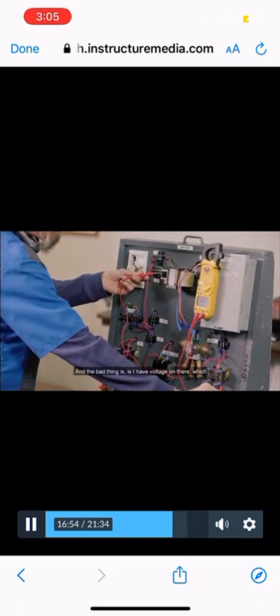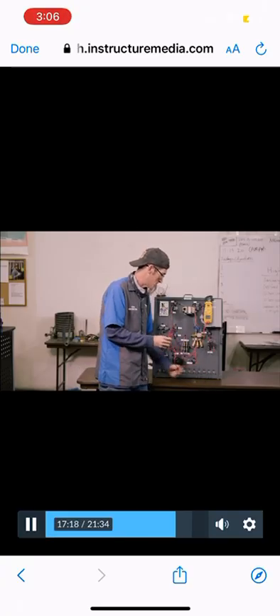So what I'm going to do is check this blue wire first, and I'm going to go from point A over here to point B over here, and I'm looking for 0 because that would be a good wire. And I have 0, which means that wire is okay. So I have to check the other side. So I'm going to go from this terminal here up to the common on my transformer. I'm looking for 0, and the bad thing is I have voltage on there, which tells me that the wire going from here back up to here is broken, and that's what's preventing this from getting any power. So the students would log that in the field. We would fix that wire. You'd be able to see it. It's either cut, broken, maybe it pulled out of the little connector. Maybe the guy before you didn't crimp that wire down enough and it's pulled out of there. Okay, so the students would log that and they'd move on to the next one.